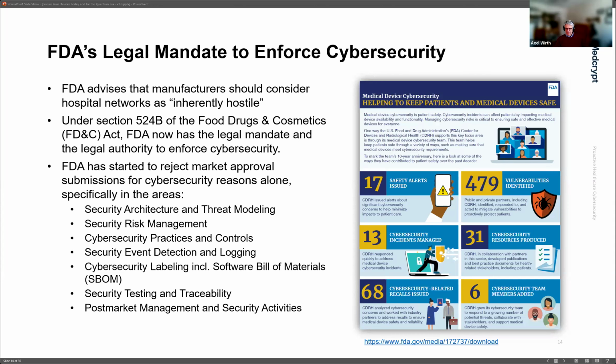And then, of course, your obligation to provide post-market management activities so that fielded devices are analyzed from a security perspective, but also that you can address any new security risks that you find in the post-market.